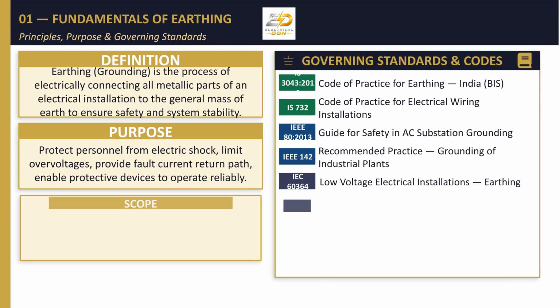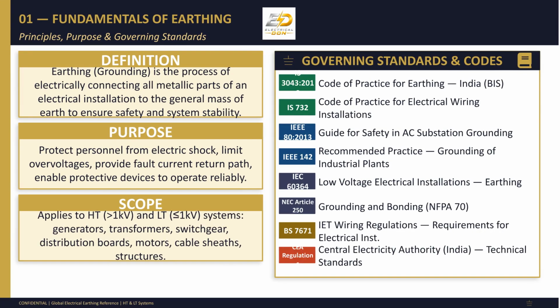earth electrode types. Earthing, or grounding, electrically connects metallic parts to the earth for safety and system stability. Its purpose is to protect personnel from shock, limit overvoltages, and ensure protective devices operate reliably. It applies to both HT systems over 1 kV and LT systems 1 kV and below.